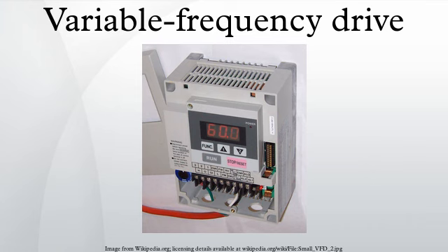In a LCI drive, a special CSI case, the DC output of the SCR bridge converter stores energy via DC link inductor circuit to supply stiff quasi-sinusoidal 6-step current output of a second SCR bridges inverter and an overexcited synchronous machine. Cycloconverter or matrix converter topologies.